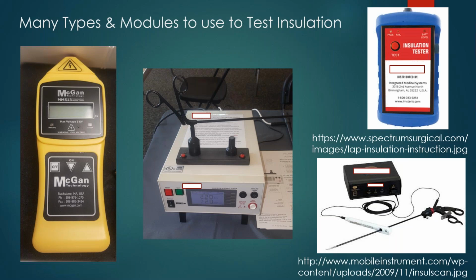Some repair vendors may provide an insulation tester to the customer at no cost, but make sure the tester meets your instrument and device inventory, as well as your staff needs based on what has been discussed so far. That's the main message I want you to get out of this: how you pick an insulation tester and accessories is based on your instrumentation and device needs, or your inventory. For example, you wouldn't just purchase a unit that tests only laparoscopic when you deal with robotics, insulated forceps and scissors, and even cords. So again, that's how you're selecting that.